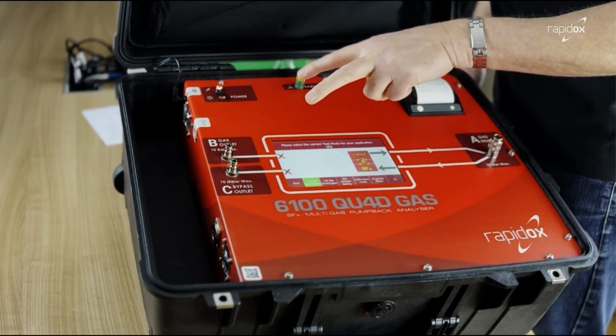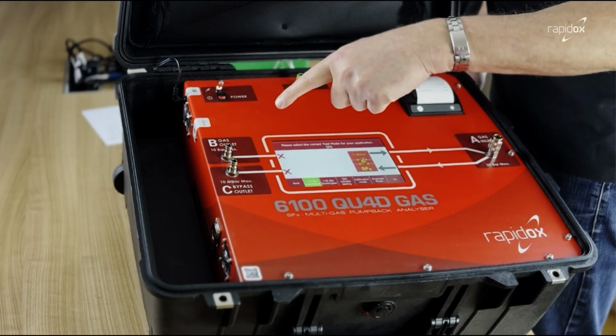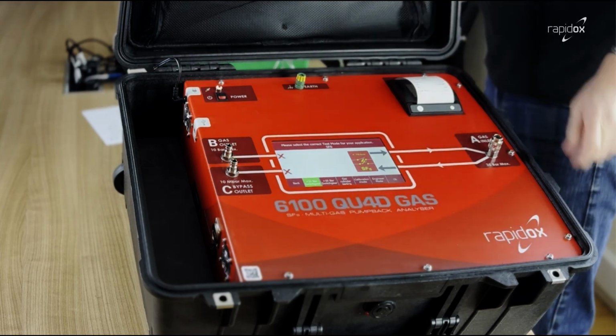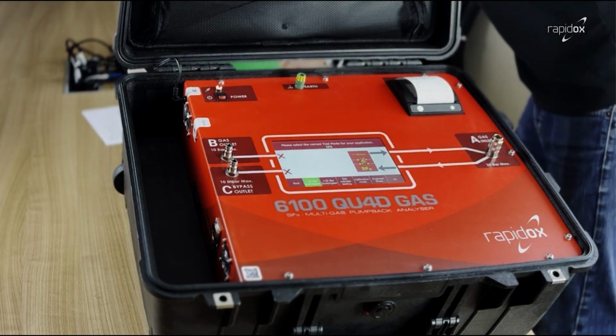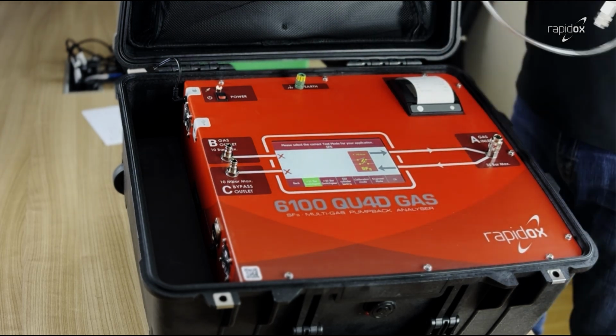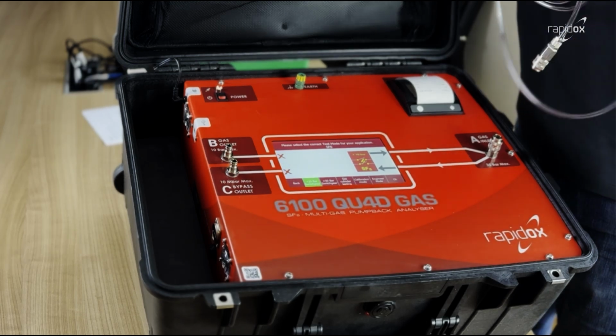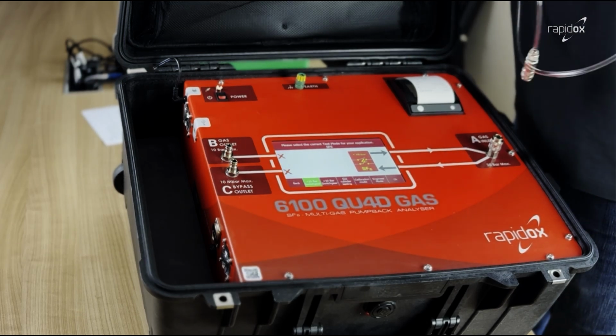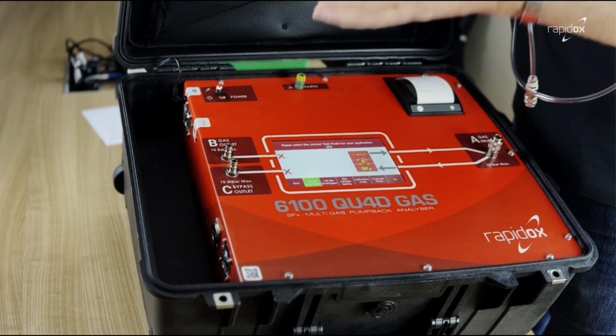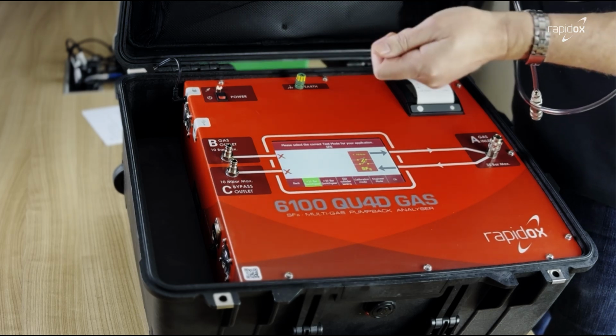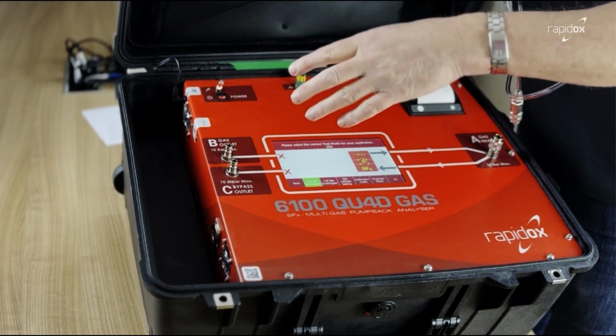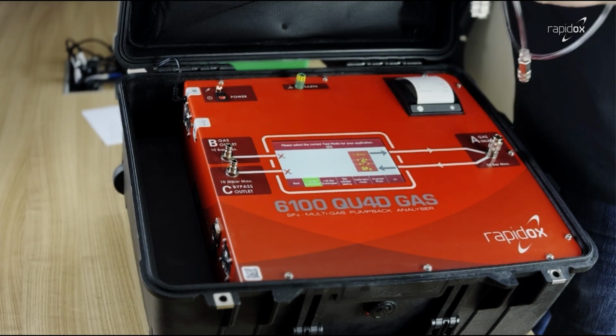Over on the other side of the analyzer, I'm now going to talk about the accessories we use on port B and port C, starting with port B. As I mentioned earlier, port B is an outlet hose for dumping waste SF6 into a portable gas recovery bag, and this is generally a low pressure outlet.